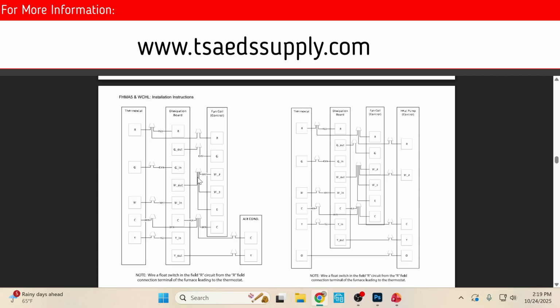And then W out kind of goes from the fan coil to the dissipation board. That's already done from the factory. And so then you're going to come into your white W1, and it goes from the dissipation board to the thermostat. And this is the straight air system. So then you'll have your common, which is brown. And a lot of people out in the field will use blue instead of the brown, and that's fine.